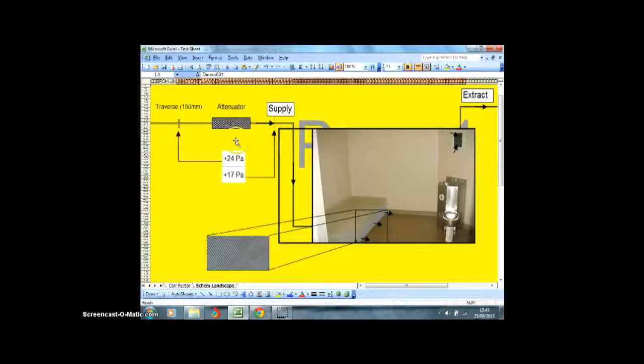Let me just briefly go to the layout sheet. It's quite crude, I drew it myself, but it gives you the general idea. The idea was to do a scan of the entire system. Say for instance there were 15 holding cells on one system. What I was able to do was pre-commission the system and open all the VCDs. It wasn't too important whether all the doors were open or not. I'm looking for a small volume, and I did run an exercise where some doors were open, some doors were shut, and vice versa, and it wasn't really much of a difference.